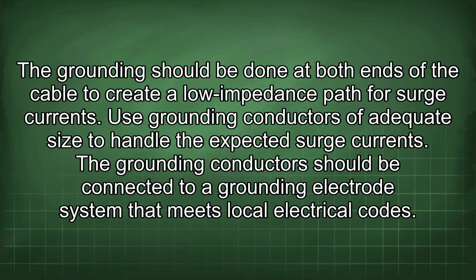The grounding should be done at both ends of the cable to create a low impedance path for surge currents. Use grounding conductors of adequate size to handle the expected surge currents. The grounding conductors should be connected to a grounding electrode system that meets local electrical codes.